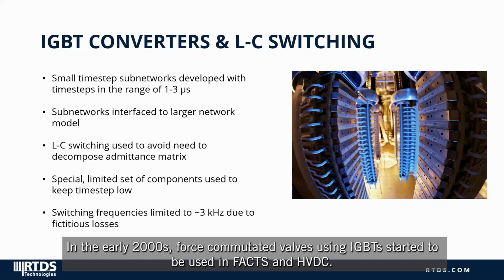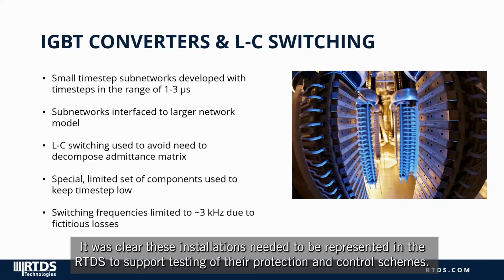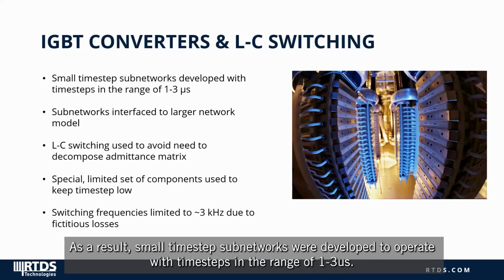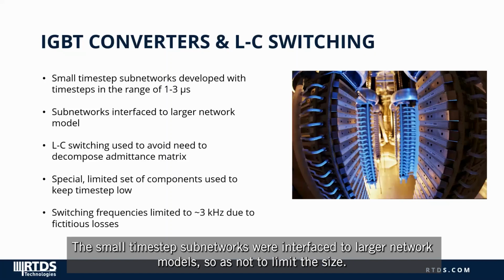In the early 2000s, force commutated valves using IGBTs started to be used in FACTS and HVDC. It was clear these installations needed to be represented in the RTDS to support testing of their protection and control schemes. As a result, small time-step subnetworks were developed to operate with time steps in the range of 1 to 3 microseconds. The small time-step subnetworks were interfaced to larger network models so as not to limit the size.